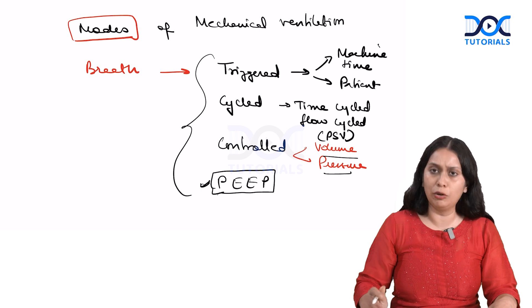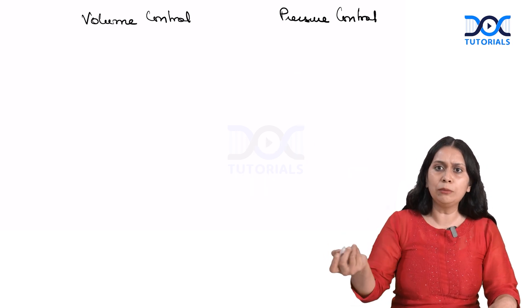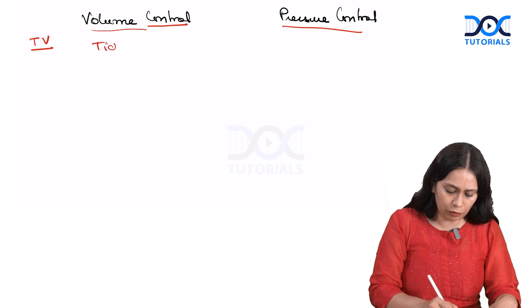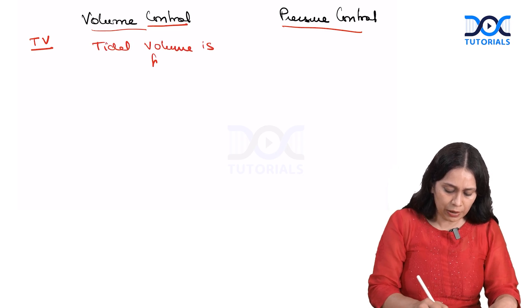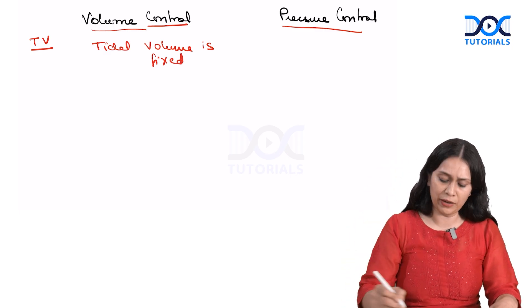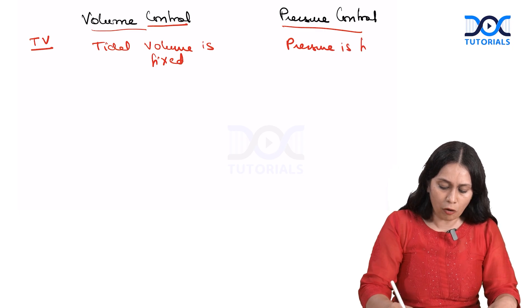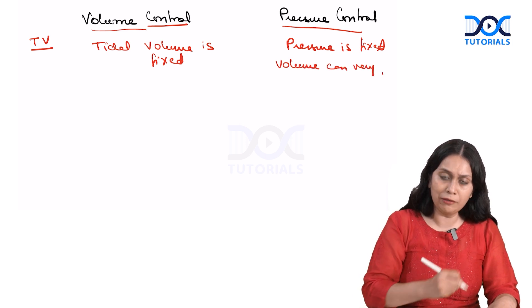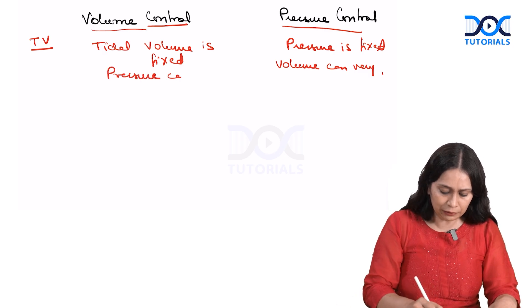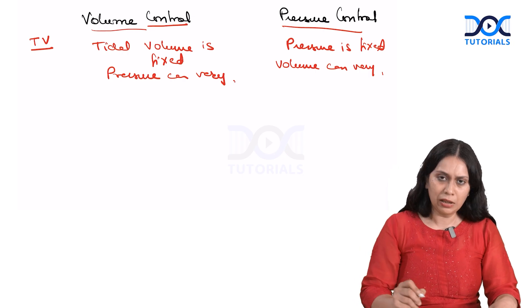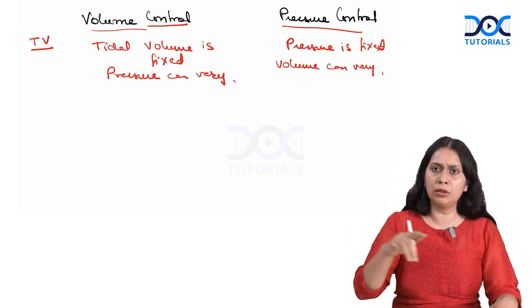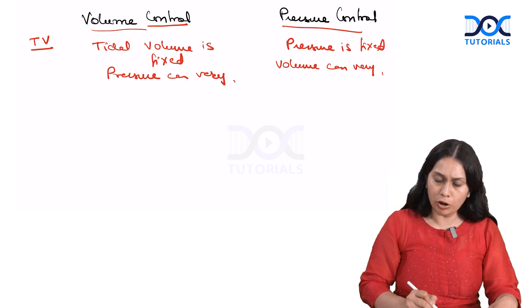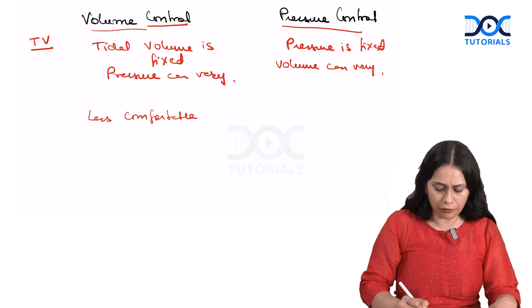Let us talk about volume control and pressure control. When we set a mode, most modes can be either volume control or pressure control. In volume control, tidal volume is fixed. In pressure control, the upper limit of plateau pressure is fixed, and the volume delivered depends on the compliance of the lung — so volume can vary. In volume control, the inspiratory flow is constant throughout inspiration until the total tidal volume is delivered, which is less comfortable for the patient. Pressure control is more comfortable.